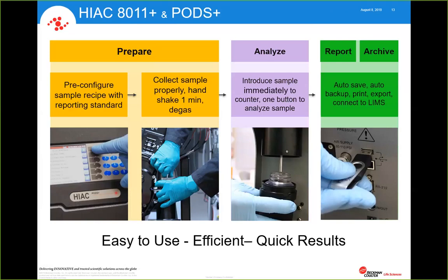In this case, gravity is not our friend. If there's metal particles, heavier particles, those will drop out of suspension fairly quickly. And so we want to make sure that we have an efficient process so we don't lose those particles out of suspension. Once your prep is done, again, agitation, degas, and then introduce the sample bottle to the system, push the button, let it run a sample, and then at the end of it, you can report it, you can archive it, you can print it, you can export it, all available on either one of the 2 instruments.